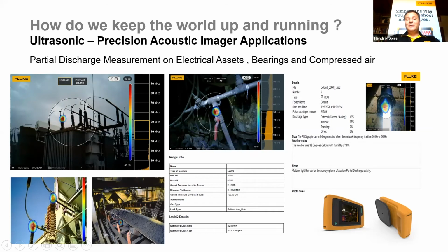So what's nice about the Fluke II910, it can actually do partial discharge measurement. So this actually measures the actual events per second happening on the sinusoidal wave. And because we are using 64 very highly sensitive microphones that detect from 2 kilohertz up to 100 kilohertz, we can basically detect this activity, and now we can quantify it. And we can then, with reporting, as you can see here, with a report, we can then basically tell you what type of discharge is this. Is it external, which is corona arcing?